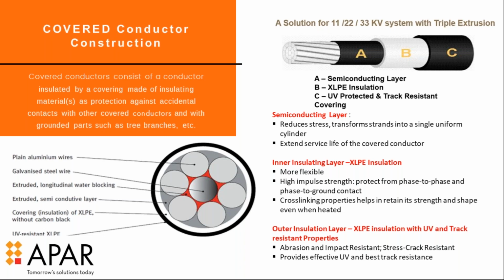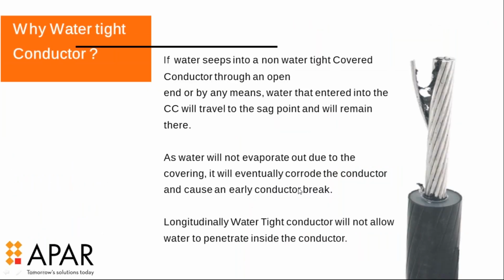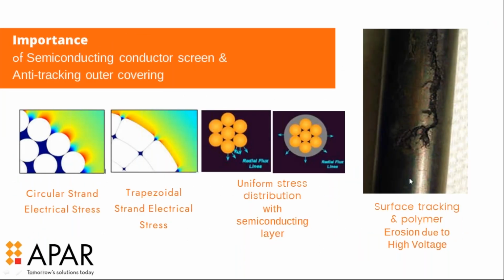When you put these cables on overhead lines, because of the lot of pollutants and dust in the air, this dust settles down on the surfaces. When dust particles settle and there is a leakage current present, this current will get a path to track through, and once it tracks through, it will create cracks on the surface over time. If the cable is not track resistant, its life will not be more than a year. So it's an important aspect that the outer layer sheet should be track resistant.